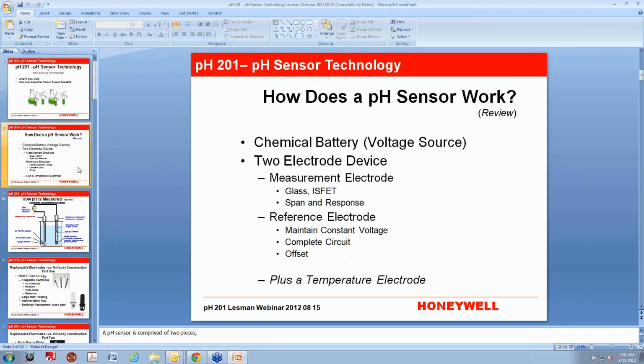If you attended the last seminar, hopefully you'll remember this. Just a quick review on how a pH sensor works. A pH sensor is like a chemical battery. It's a voltage source. It generates its own voltage signal. It has two electrodes, a measuring electrode and a reference electrode, plus a temperature sensor. The measuring electrode is either made of pH-sensitive glass, or it's an ion-sensitive field effect transistor. And it is responsible for the span and response of the sensor.